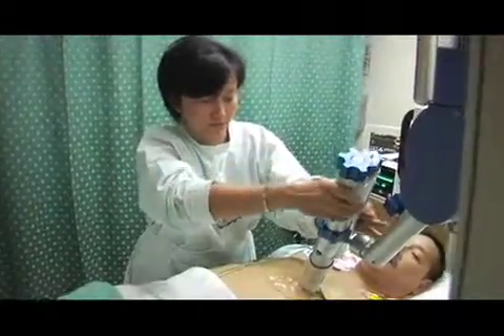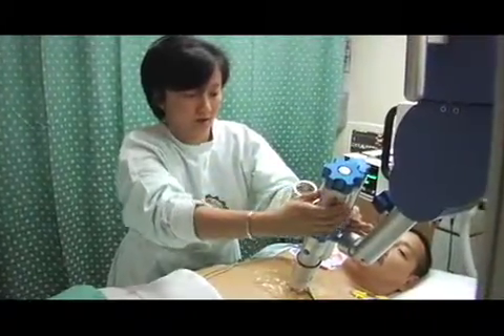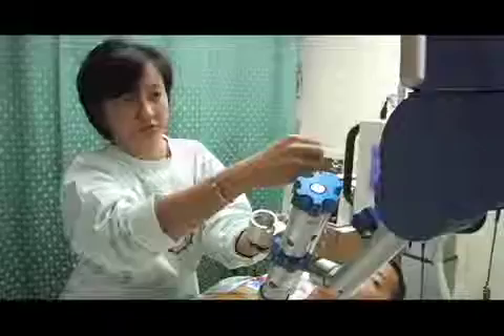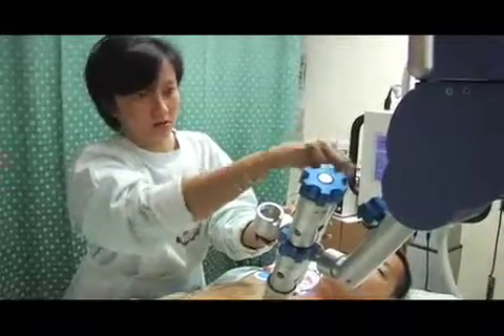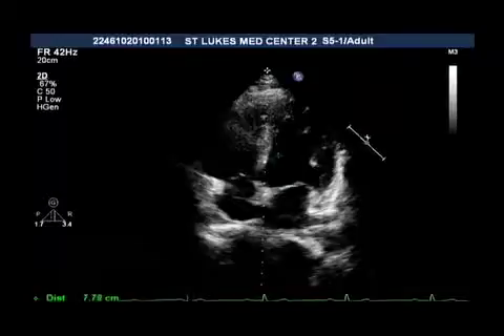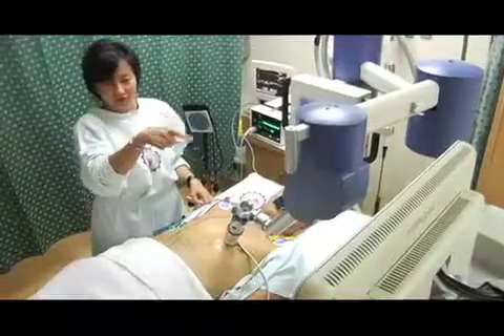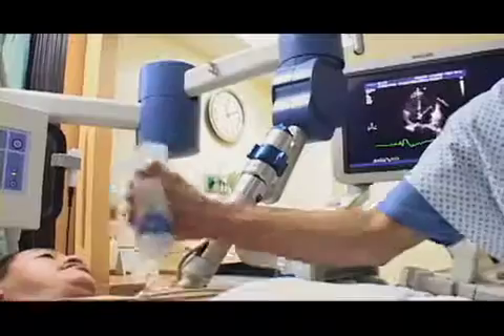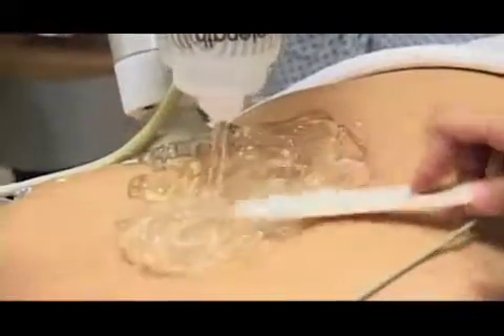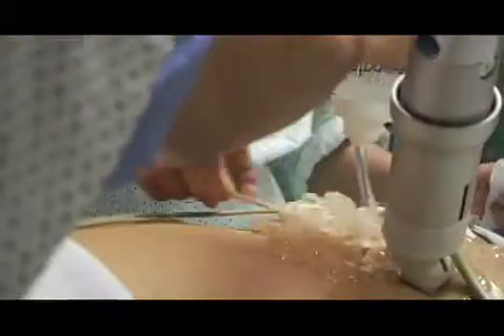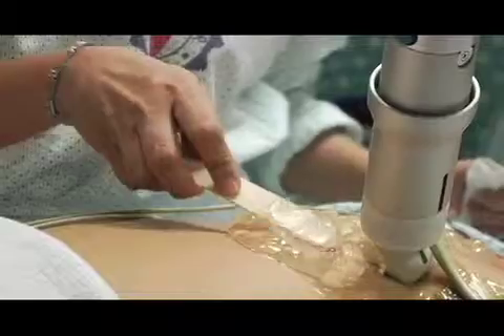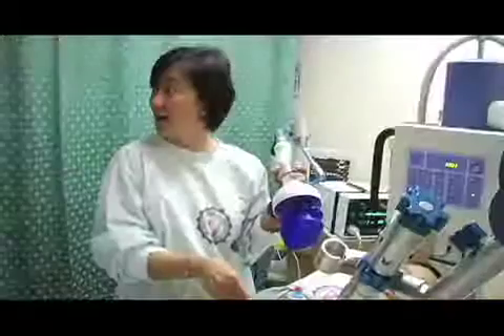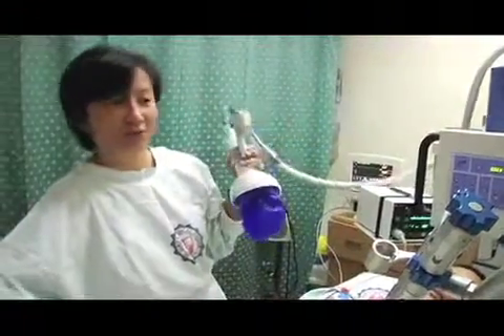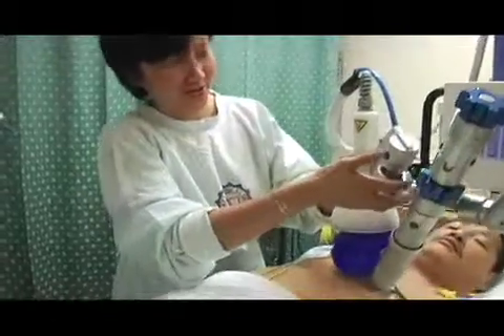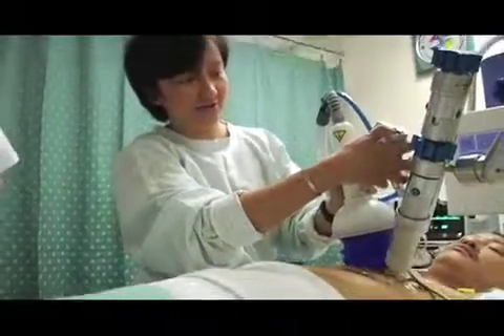The shockwave applicator is turned to the right side of the ultrasound transducer, toward the sternum and the costal area. The treatment site is placed on the ultrasound screen center axis. Ultrasound gel is extensively applied between the membrane and the patient's skin to maximize the electrohydraulic effect. The shockwave applicator is inflated until there is good contact with the patient's skin, and wrinkling of the membrane should not form.